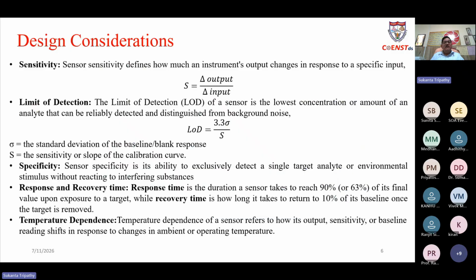Sensitivity you can find from this calibration graph. If you find the slope of this calibration graph, this will give you the sensitivity. And once you know the sensitivity, you can also find the limit of detection, which is the lowest amount of the physical quantity you can measure using this sensor. As you can see in this relation, the limit of detection can be calculated from the sensitivity and the standard deviation. So once you know the standard deviation and the sensitivity, you can calculate this limit of detection.